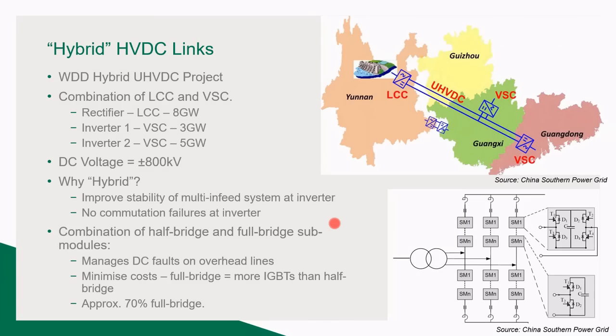And then there's the idea of the hybrid. This is where you take the benefits of one technology and of the other and discount the cons. So this is an interesting one up here. This is a project under development, where they need to go from a hydro station to the loads, understanding that a VSC is a more robust solution into these kinds of loads. They're proposing to make the inverters VSC, but the rectifier LCC. So with the 8 gigawatts, it's taking advantage of the low losses of the LCC, and of course it's going to be a very strong connection. And on the rectifier, you generally only have commutation failure issues on the inverters. So it's a nice solution, taking the benefits of both technologies.